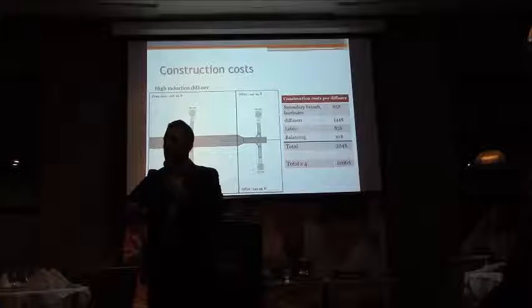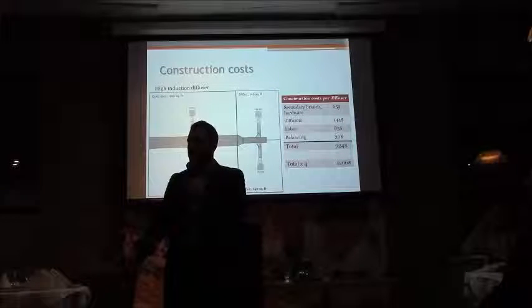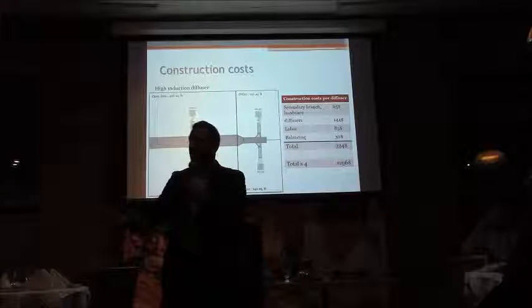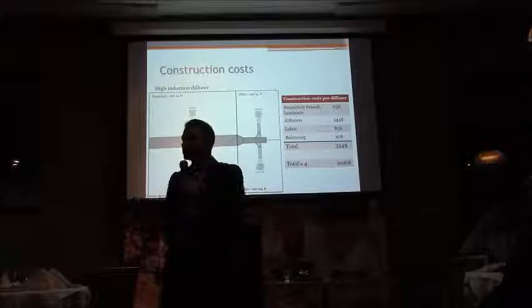The same goes for the domes that you install on the wall, the low velocity air displacement diffusers. They exist, a lot of manufacturers have them, but we don't use them in Canada because with low velocities you can't heat, since your air is going to go straight up to the ceiling. It's only valid for cooling mode. So this is another type of diffuser that exists that we just don't use here in Canada.